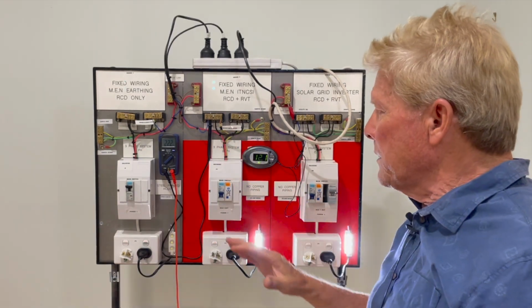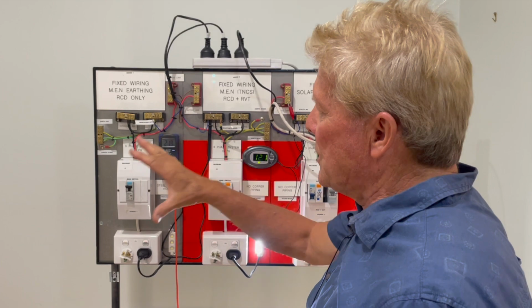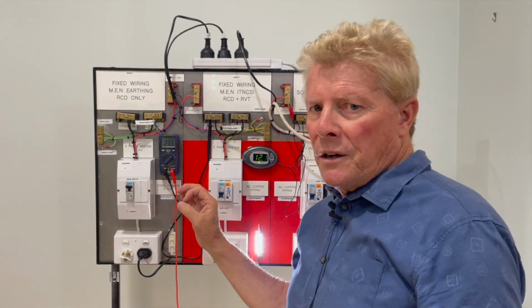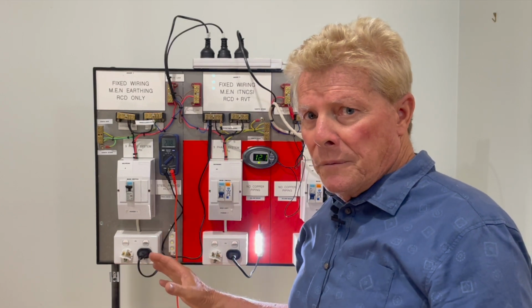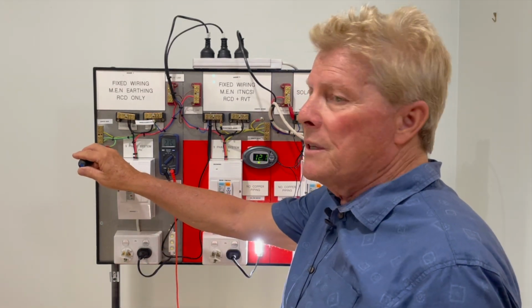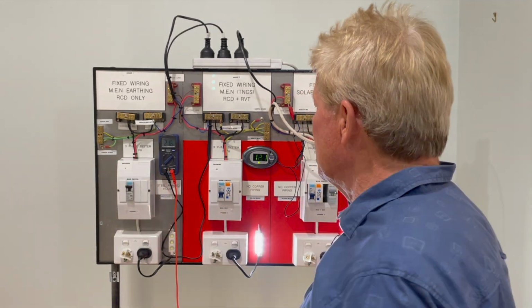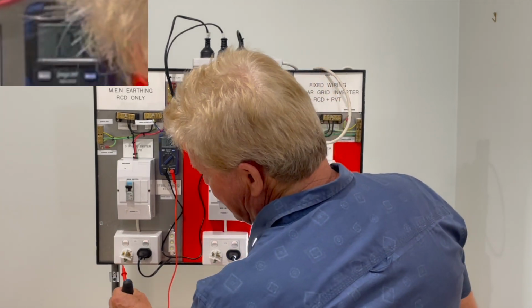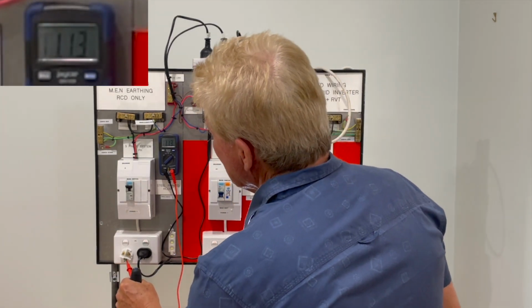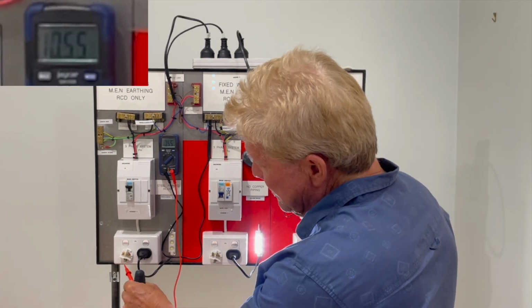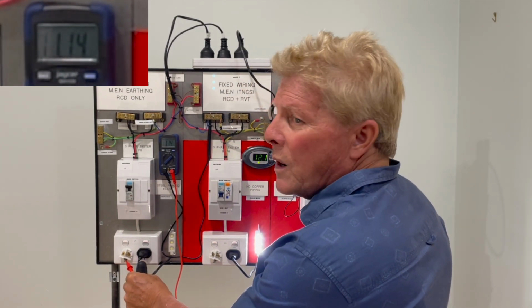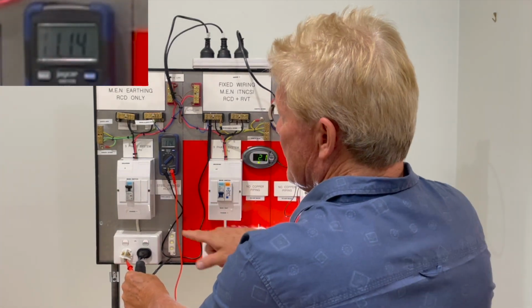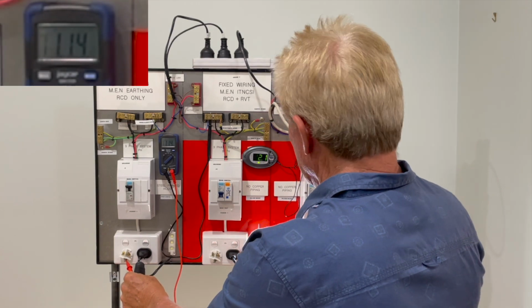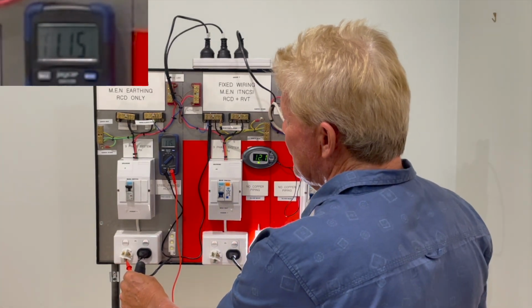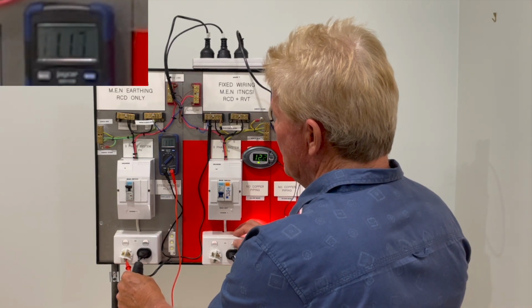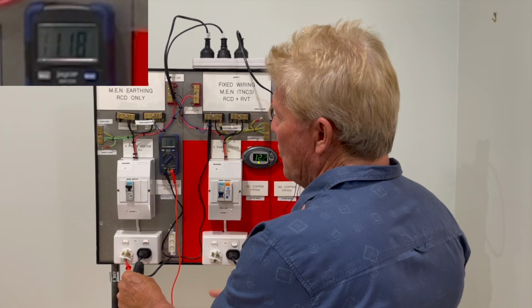And that's what happens with your lost neutral. The risk is you don't know you've lost your neutral because your lights and power are on. But this is so dangerous because this point up here is live. It is completely live. So when we go down to say this point here, you get 11 volts. Right there, 11.1. That's because it's going through all these loads. So if we turn the loads off, it goes up a little bit, goes up a little bit more.